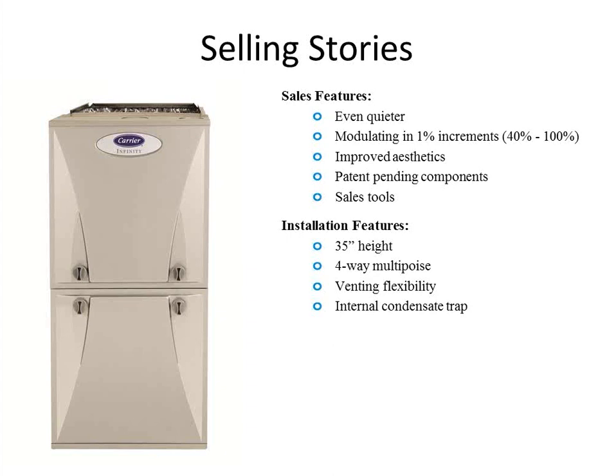And then 5-10 minutes later, whenever it is, there's another call for heat, and they turn the furnace back on at a calculated predictable starting point based on the previous cycle, and then they ramp it up again from there. What we do differently is we don't shut the furnace off. We continue to leave it on, and instead of shutting it off, we ramp it down. We ramp it up and down continuously to always give you the exact number of BTUs that you need to satisfy the demand. We'll kind of explain that a little bit later on today. So there's definitely a difference in how the gas valve operates compared to non-Bryant and Carrier systems.